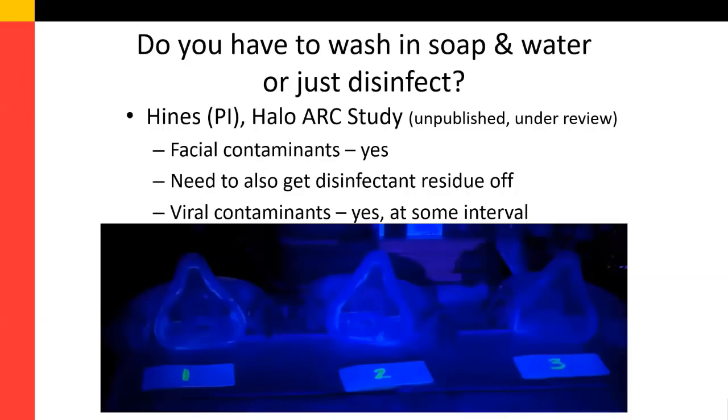So we recently have been involved in research on this topic with use of a hybrid PAPR elastomeric product called the Clean Space Halo respirator. In this respirator, there's a face mask that is silicone-based, and it looks similar to what you see with an elastomeric respirator. It would be very simple if all you had to do in a hospital setting was wipe down that face mask with a disinfectant wipe, and you didn't have to include that cleaning step with soap and water. So this is what we tested.